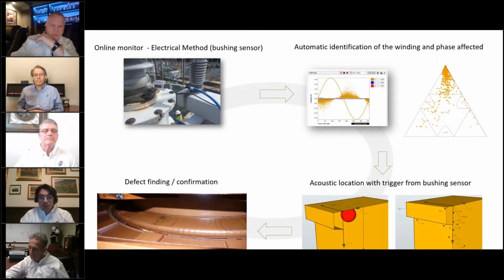The PD monitoring system was able, in this case, to show that there actually was a partial discharge. You can see here the partial discharge phase-resolved pattern showing the activity. In this easy representation, this is a ternary plot inspired by the Duval triangle, which we use for partial discharges.